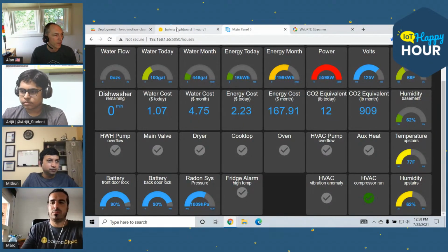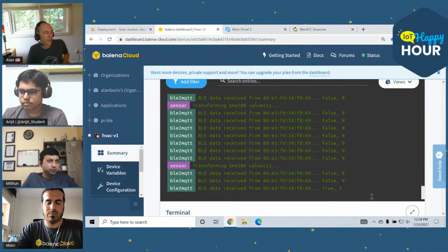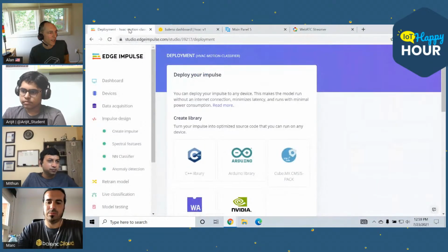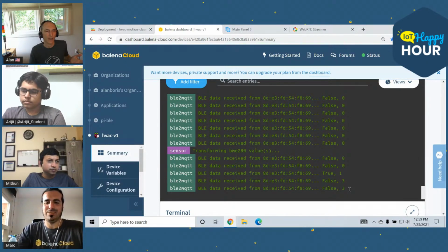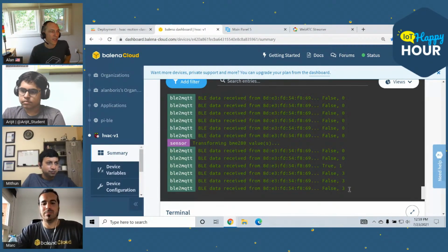Okay, so the compressor's gone on. There's a little lag here, but now it's showing an anomaly. Here's what one anomaly looks like. That's just a momentary anomaly because there are so many different types of vibrations in the transition from one state to another. It's gone to 3, which is startup. That's the correct vibration. It's detecting that the compressor has started up, which is that very distinct resonance on the system. And in a few seconds, you'll see it go from 3 to probably 1 or 2.